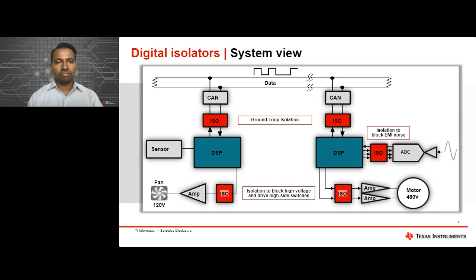Let's take a look at some of the insulation types. Functional insulation is insulation needed for the correct operation of the equipment. It is typically referred to in motor drive applications or high side switches, where isolation is not necessarily used for protection. It is used to enable high side driving or high side switching. Without an isolator, you won't be able to achieve it. That's why it's called functional insulation.